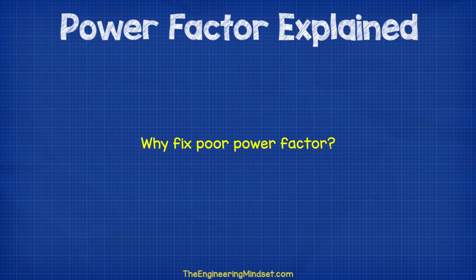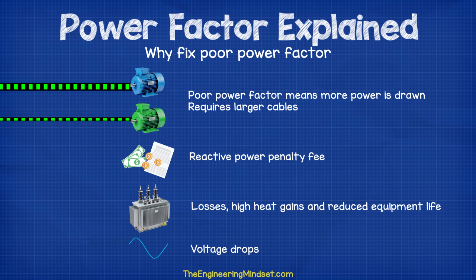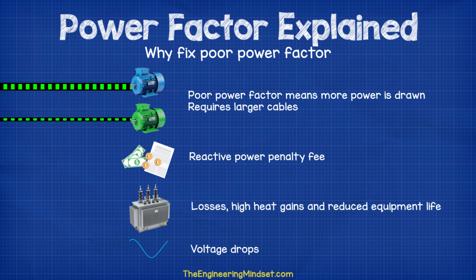So why should we fix poor power factor? Poor power factor means you need to draw more power from the electricity network to do the same amount of work. Therefore, the cables need to be larger, so the installation is going to cost more money. If the power factor becomes too low, the electricity supplier might charge you a penalty fee or a reactive power charge. Poor power factor can cause losses in equipment like transformers, leading to high heat gains, voltage drops, and can even reduce the life expectancy of equipment in extreme scenarios.